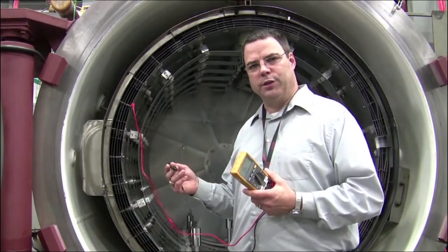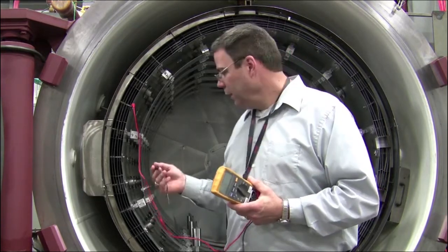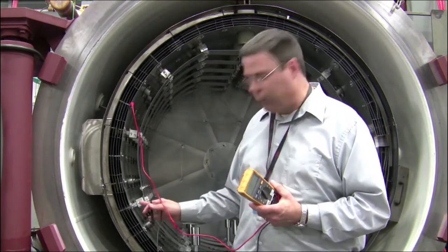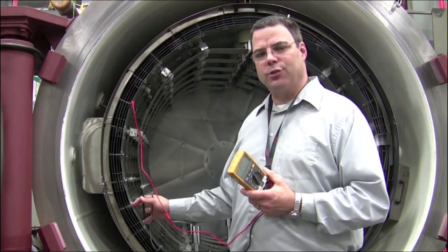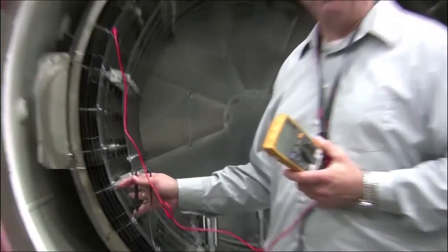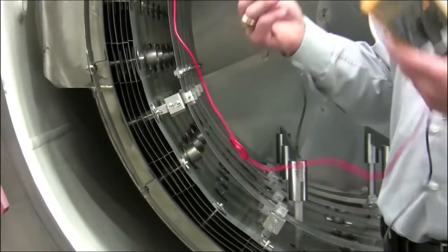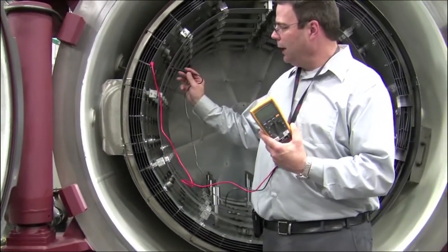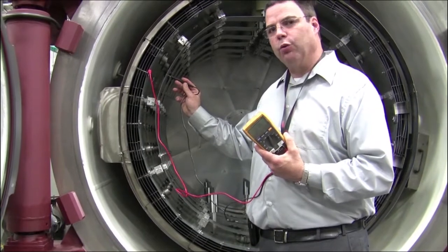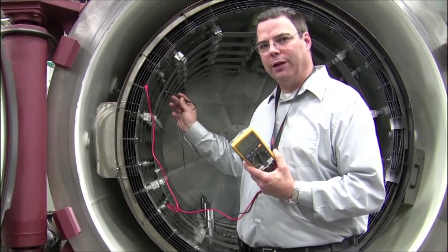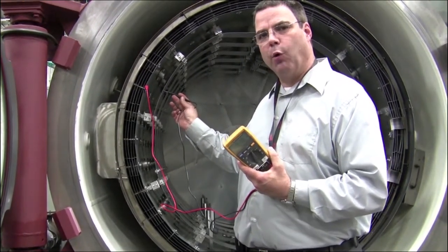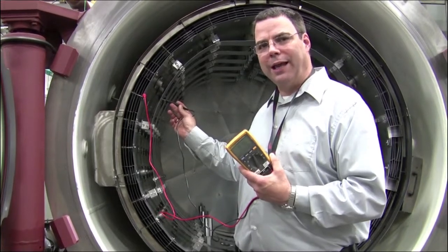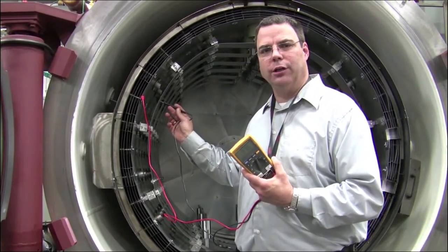The secondary reason for the resistors, and most importantly, is the ability to troubleshoot the ceramics and ascertain the life cycle of your ceramics when they need to be changed. A simple standard loop ohmmeter from ground to the heating element will read through that resistor, and I should have a reading of 97 to 104 ohms, which indicates that my ceramic condition is near perfect.